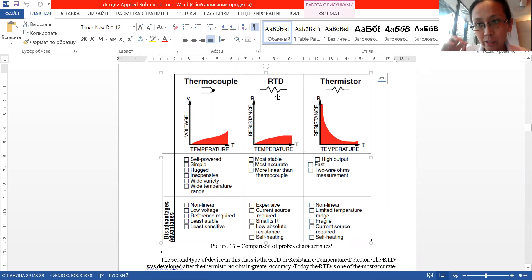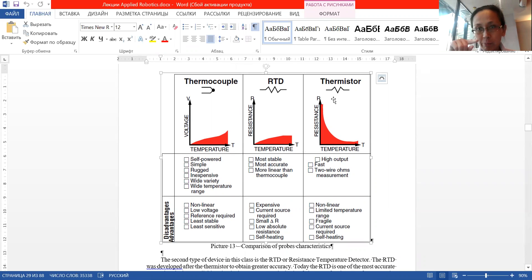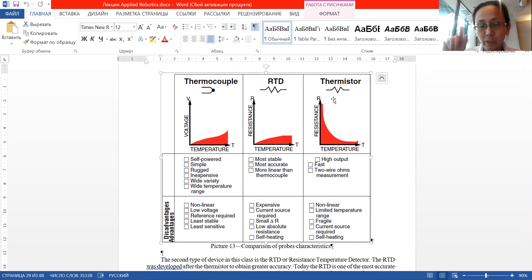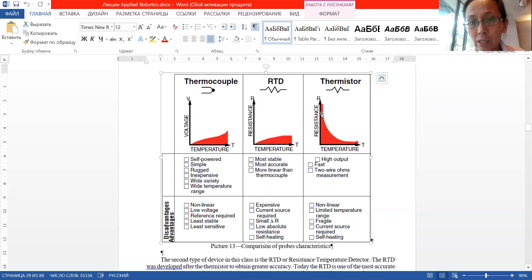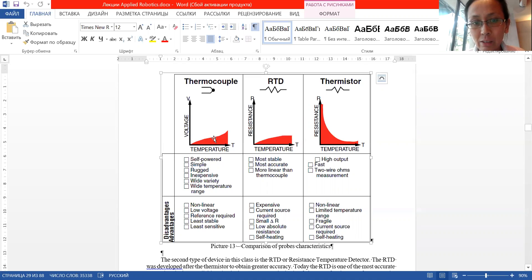So we have thermocouples, RTDs that work on pure metals, and semiconductor thermistors. Looking at linearity: thermocouples are a little bit nonlinear, RTDs are almost linear, and thermistors have a highly nonlinear signal. So the most linear are RTDs, thermocouples are more nonlinear, and thermistors are completely nonlinear.